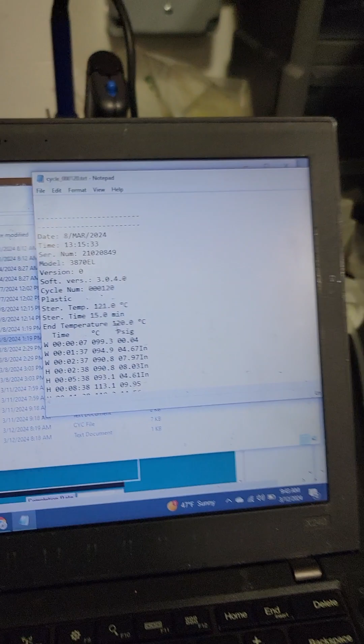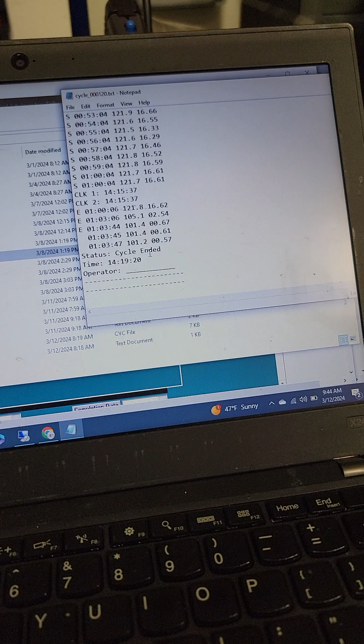And then here's a passing cycle: boom, boom, boom, 116, 117. All I did is move the needle valve a bit. Look, we got to 121, 17.10, sterilization started, held, continued, clock data, and then exhausted. That was it. Alright, so that is how you get cycle data from the unit, and this is what it looks like in a text file.